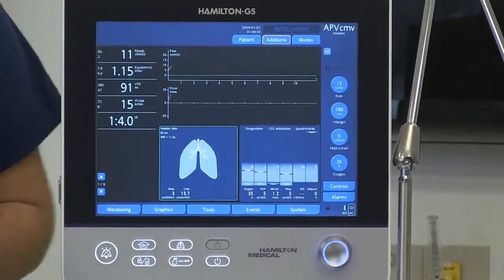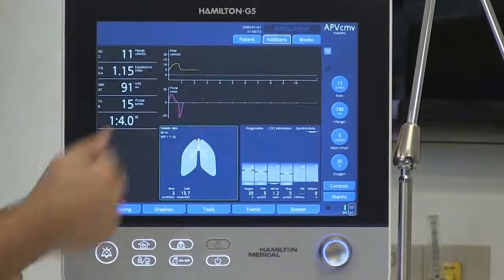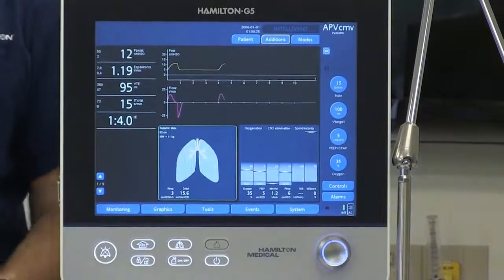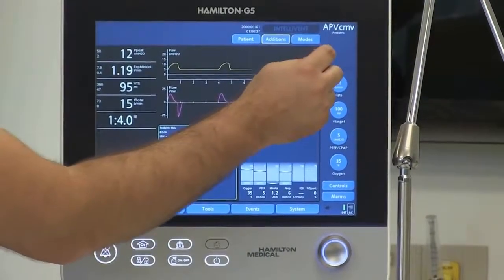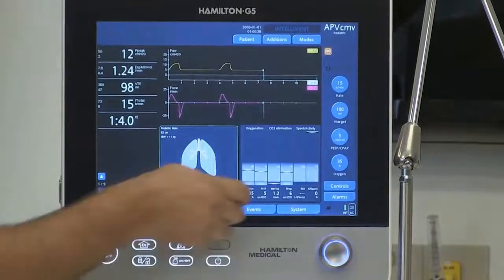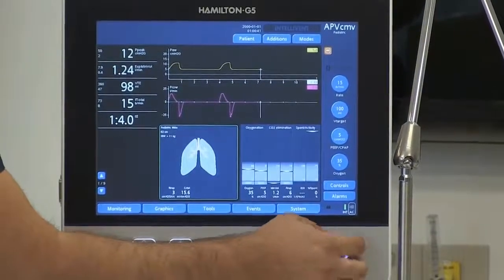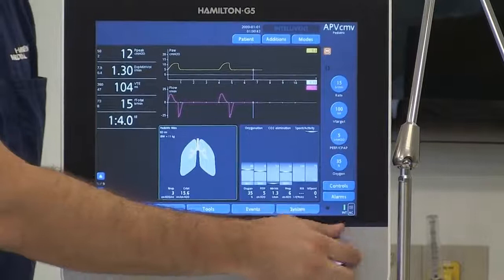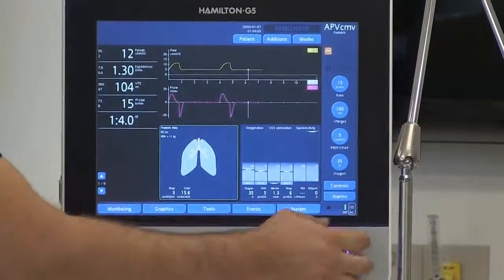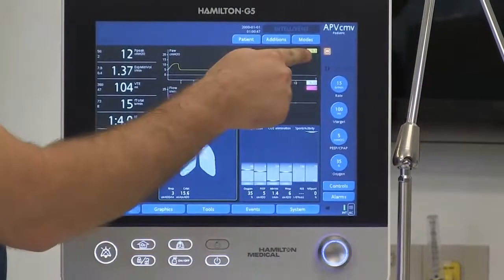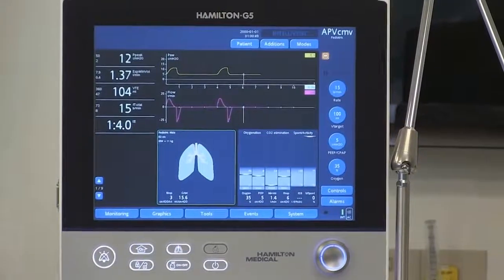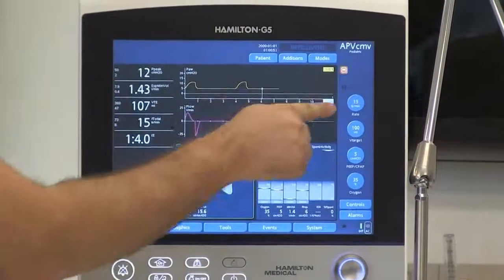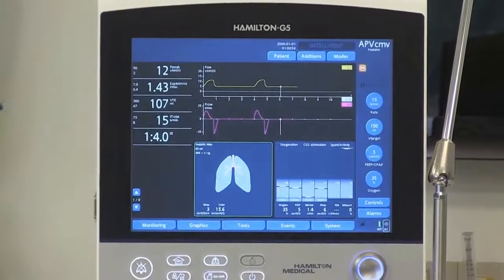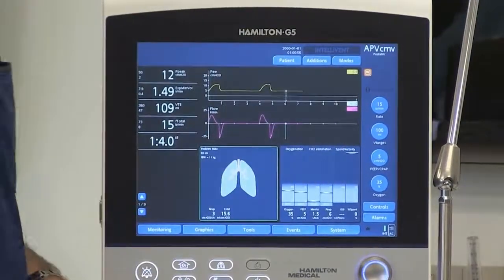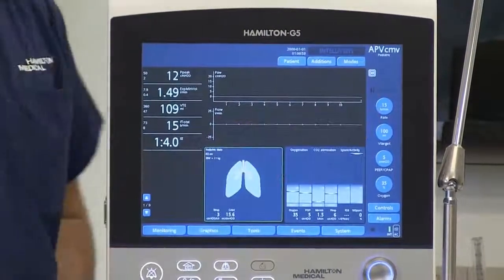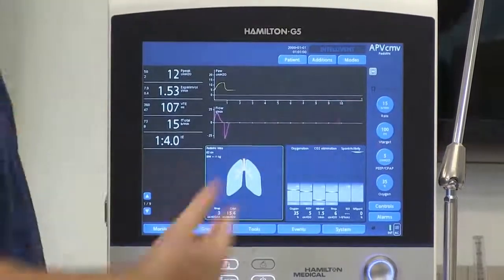Mode section, we already went over. The button over here, which looks like an elevator door close symbol, is the freeze screen button. So you would press it and then use your knob to scroll back to look at any data point that you would want to see on your waveforms. Yellow values are pressure, pink values are flow, and white values are time. To take it out of the freeze screen option, you just press the freeze screen button again, and it resumes into real time.